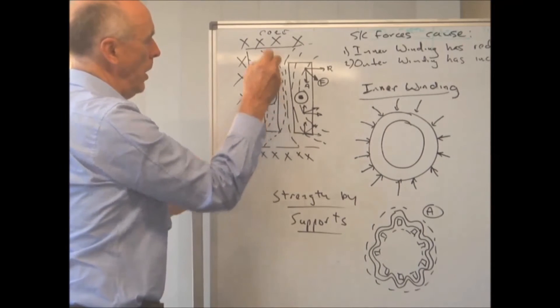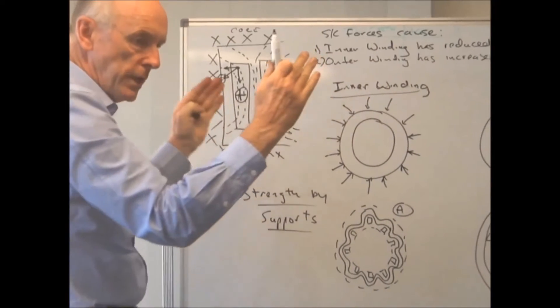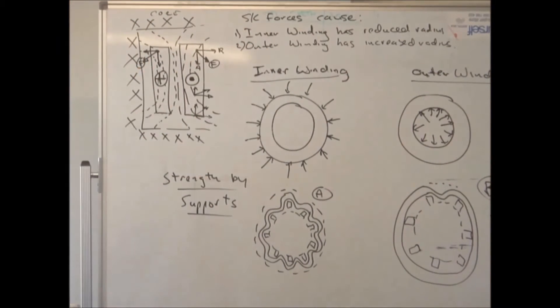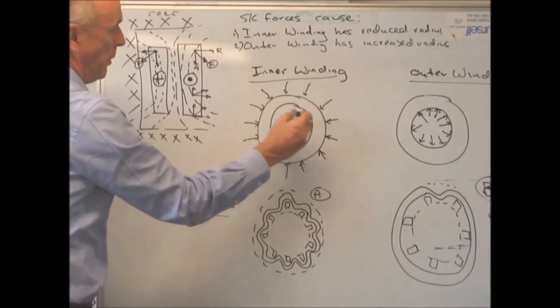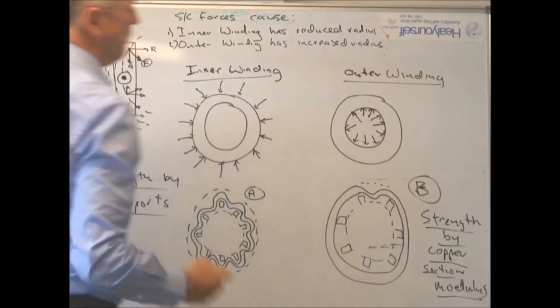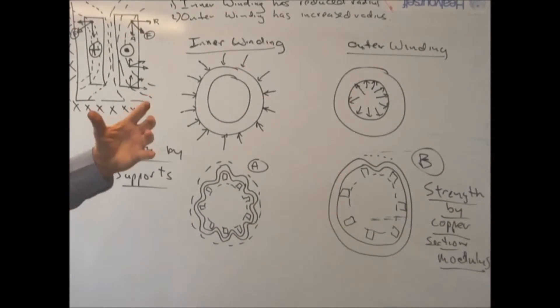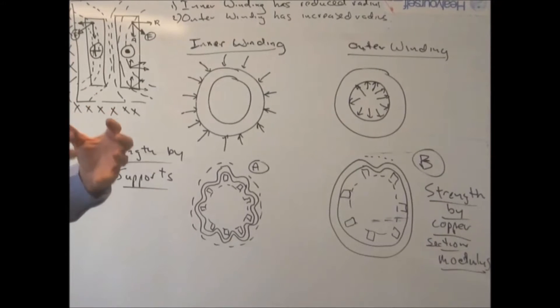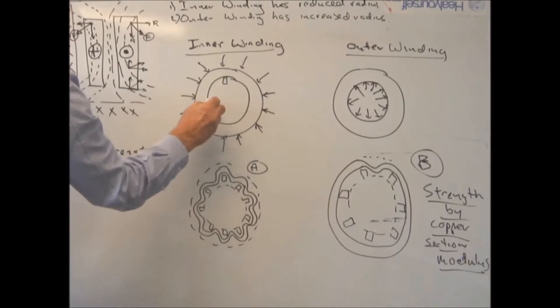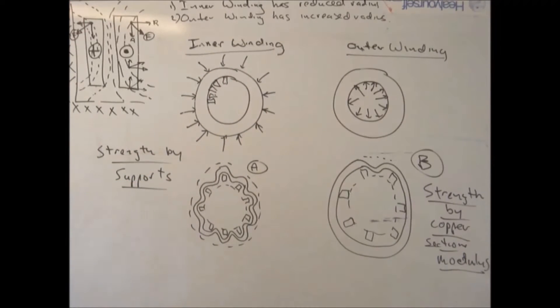Similarly, the inner winding is pushed down and compressed inward — its radius is being reduced. The outer winding's radius is increasing due to the hoop stress, the bursting force. So the inner winding is in compression and the outer winding is in tension, being pulled apart. Depending on how you support your winding, there are two methods: relying on the shear section modulus or strength of the copper or aluminium, or adding more supports inside the winding to reduce the span between support points.